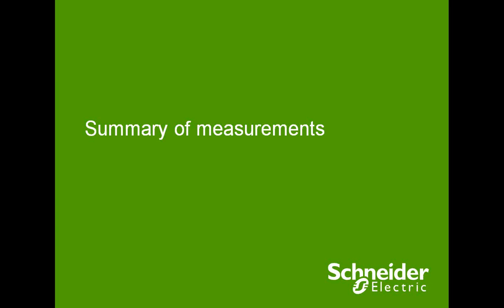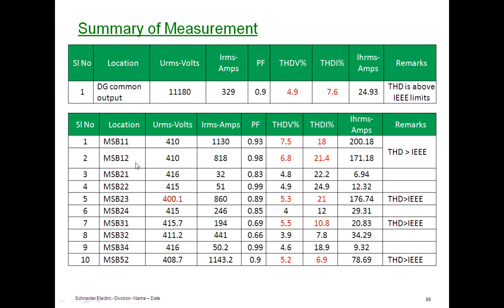So we have some measurements. We did them on the different transformer secondary sides. They are numbered MSB11, MSB12, and so on and so forth. The values you see in red are the harmonics that are exceeding IEEE standards. So we identified there are about 5 locations where harmonics are higher.